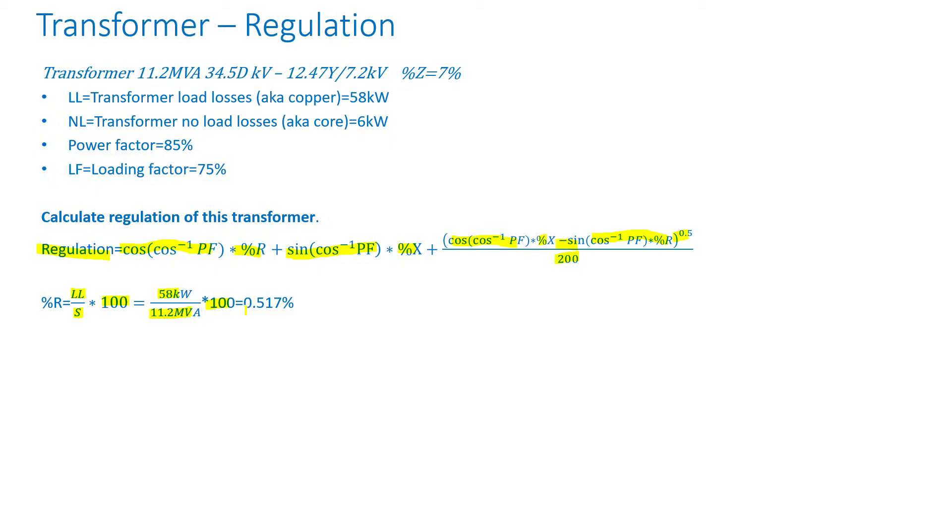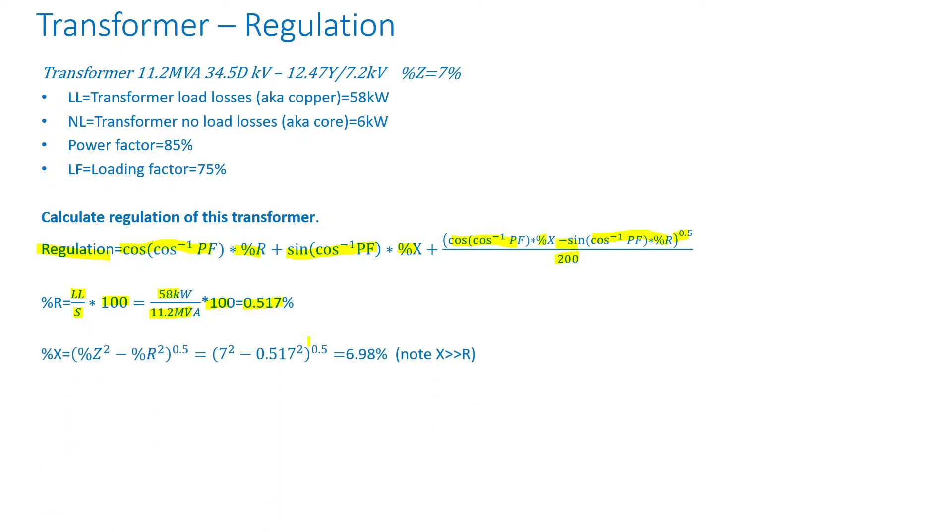So it's equal to 0.517%. And now the reactance is equal to square root of impedance squared minus resistance squared. So if I put in the numbers, I get reactance is equal to 6.98 percent. And note that typically the reactance is way bigger than the resistance.